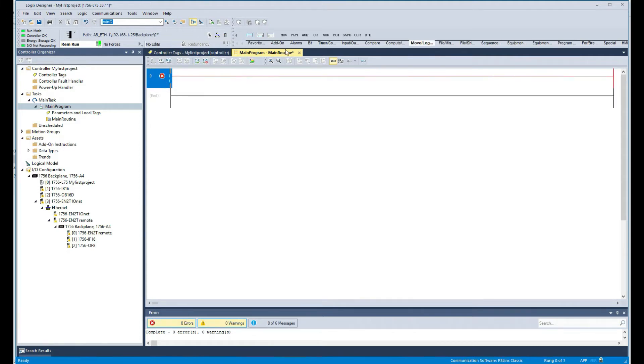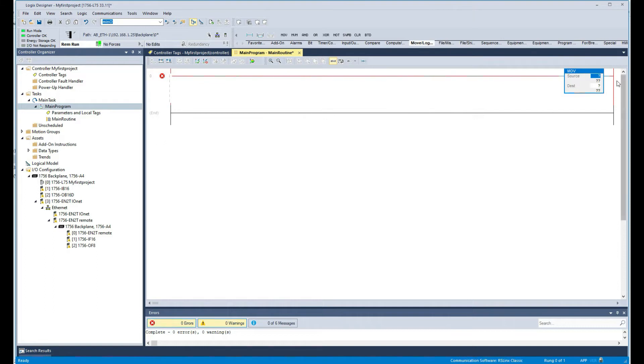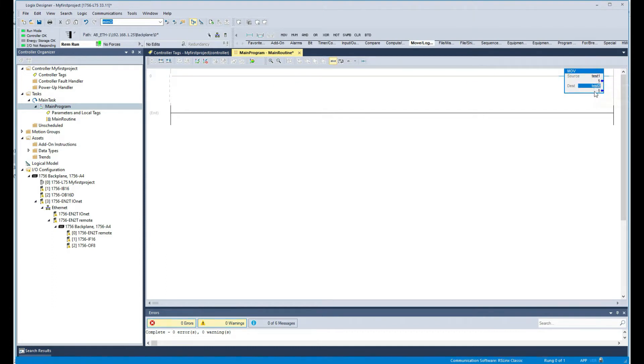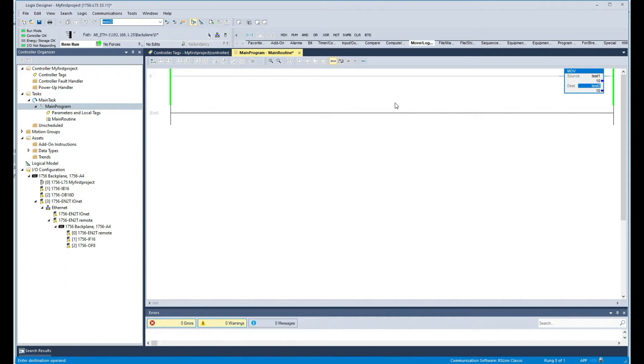The first thing I'm going to do here is add the rung and then call the move function. The move function, as the name suggests, moves a value from the source to a destination. For example, I'm going to put here 'test one' as the source and 'test two' as the destination. This will copy whatever value is in test one into test two. So if I change this to 10, you will see immediately test two also has a 10.